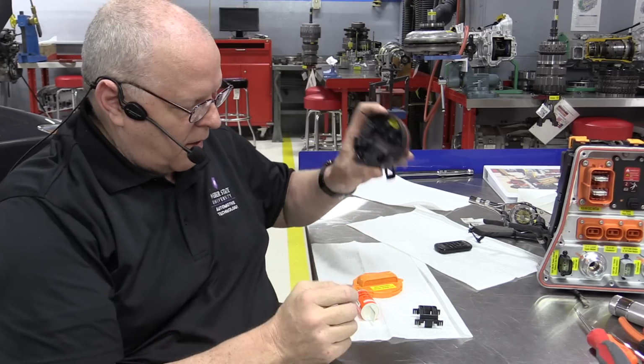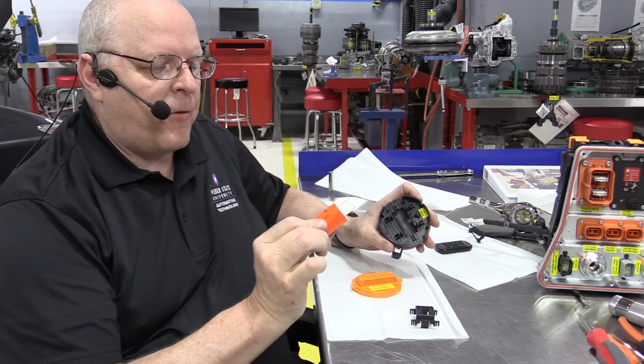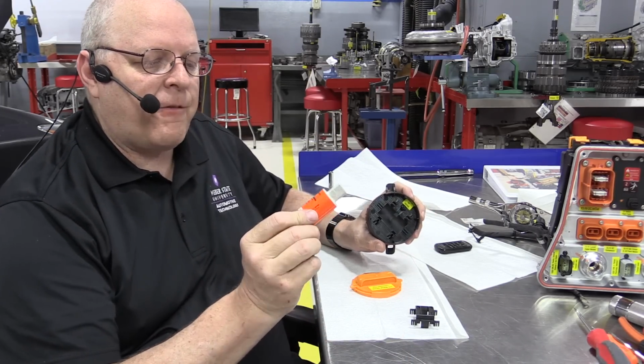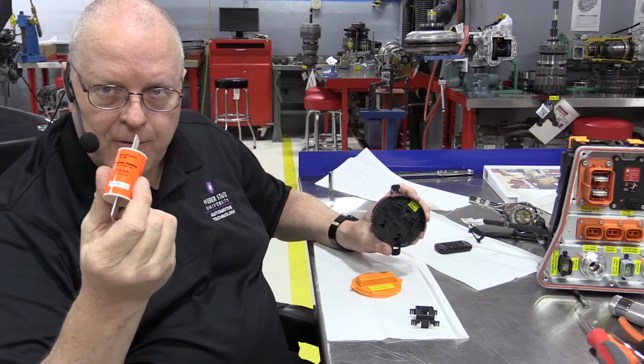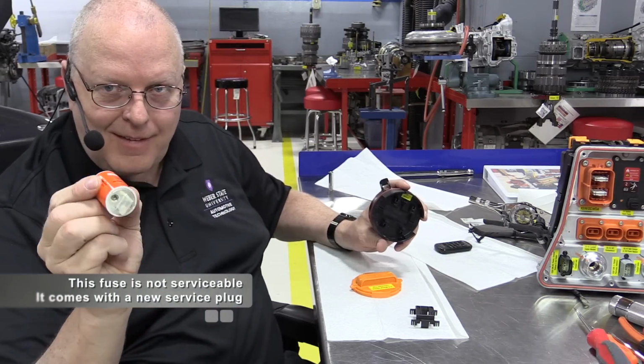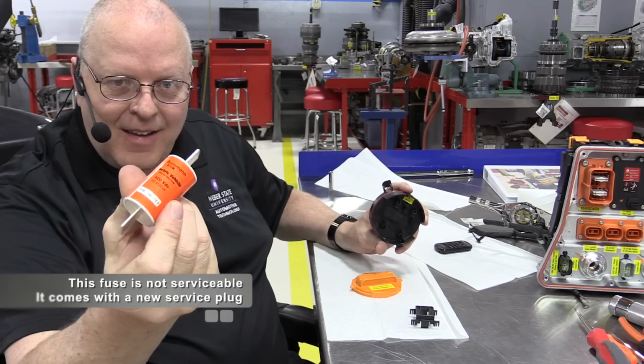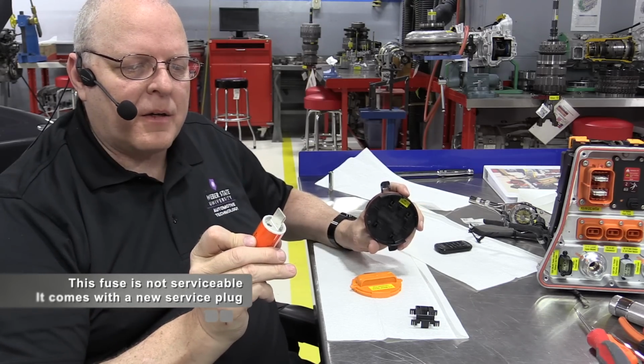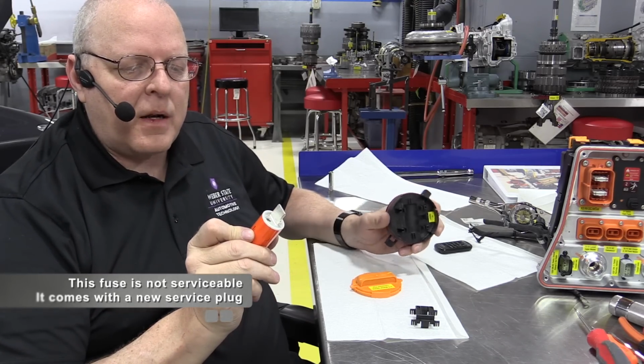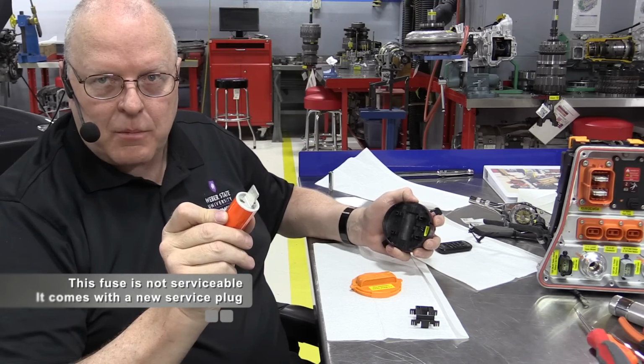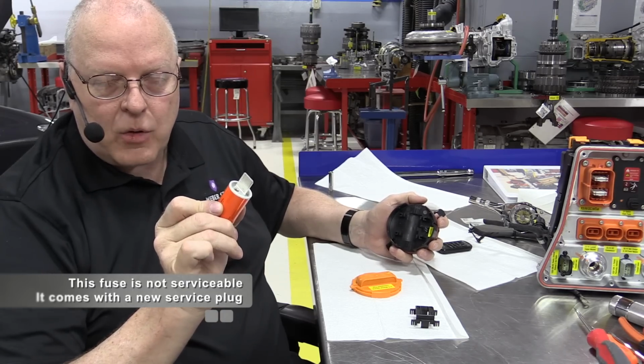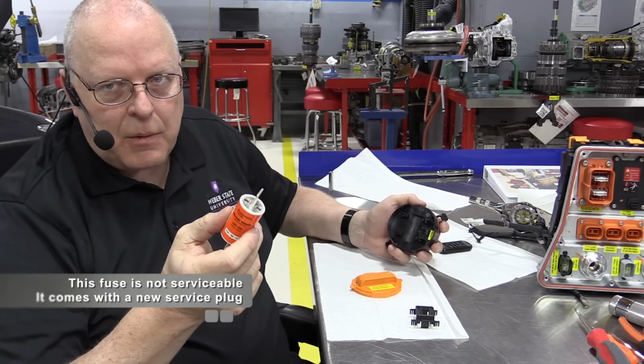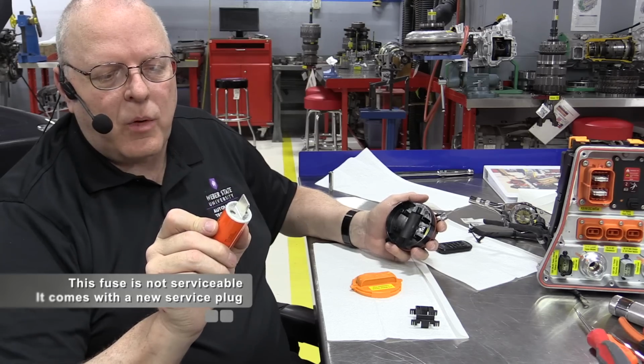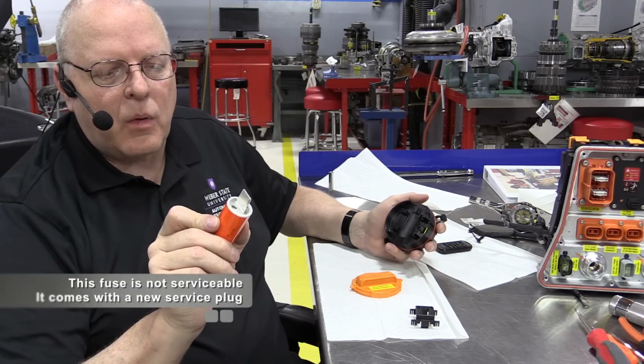So that plugs in right there. Then we have a 420 volt, 350 amp fuse. Look at this monster. It's made by Bussmann, rated at 20,000 amps maximum before it finally melts, and of course that's in a couple of milliseconds before it would blow all the way open.